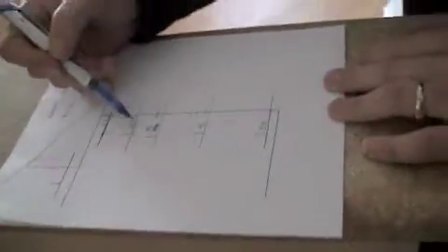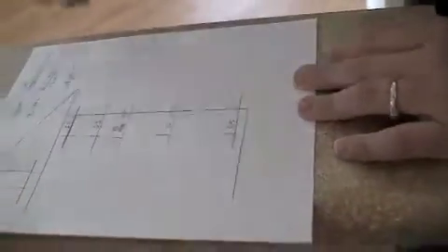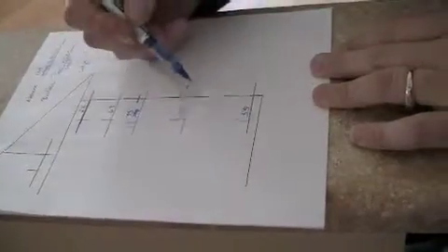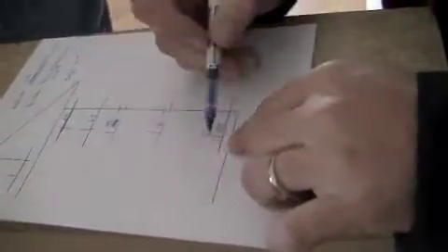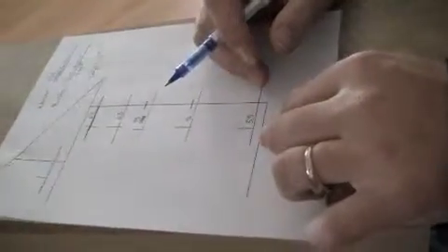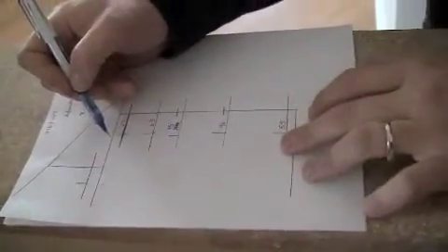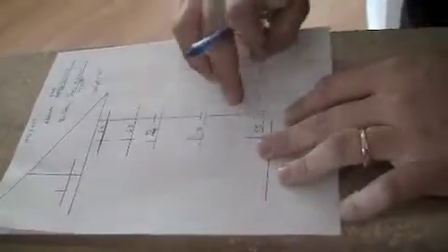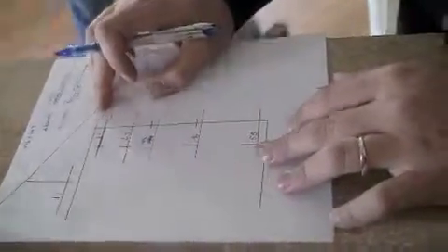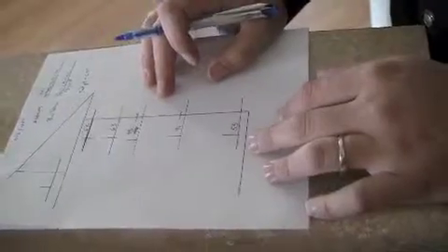So these are our inside temperatures. Then we're going to go outside and we'll measure these points, and then we'll do our deltas. Picture numbers 446 and 447, write that down. When we get the outside temperatures, we'll do our deltas, and that'll give us the idea of how efficient or inefficient each one of these point areas are. Delta being the change in temperature between the inside and outside of the house? Exactly. That's very good, Jim.